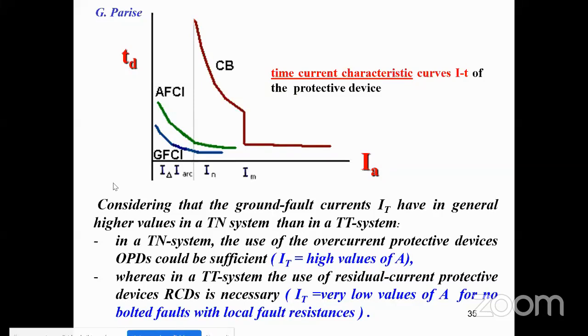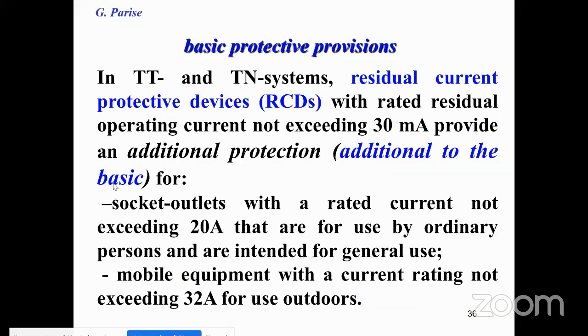But in a TT system, the use of a residual current protective device is necessary, because the current assumes a low value. In the example, we show about 20 amps. Basic protective provision: in TT and TN systems, residual current protective devices are mandatory for the IEC approach, because it considers this active protection as an additional, not a basic protective provision. The basic protection has to be always passive.